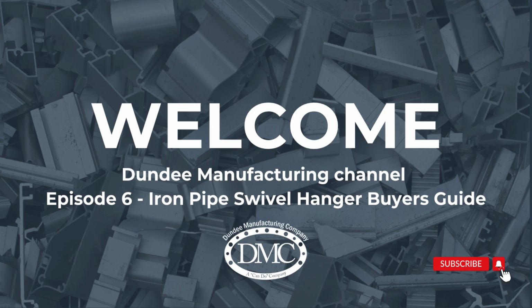Isn't bigger always better? Not when you factor in weight and material cost. Steel is expensive. Very. If the NFPA engineering calculations allow for, say, a three-eighths-inch rod instead of a half-inch rod for a specific commercial run, utilizing that thinner rod across a 500,000 square foot facility saves literally tons of steel, and thousands of dollars.